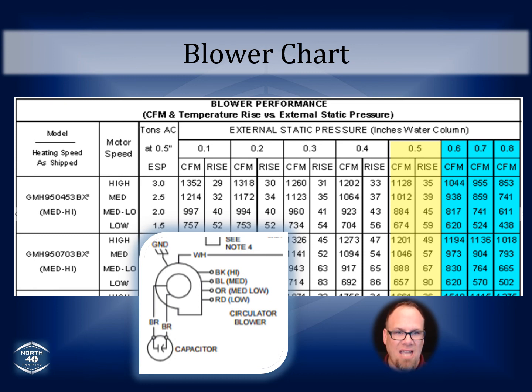You're on X fan speed, and that X fan speed correlates to your resistance across the top, right? Your static. So that would be the 0.1, 0.2, 0.3, 0.4, 0.5, 0.6, 0.7, 0.8. That's your measurement before the blower and after the blower, and you add the raw numbers.